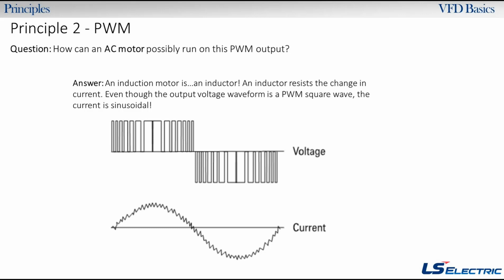Another thing to mention too is some people will connect up a multimeter to the output of the drive, and they'll wonder whether they should set the meter for AC or DC voltage. And you actually want AC, because most meters are true RMS meters, so that's root mean square. What it's going to do is add up and average out all these DC pulses. So if you set your meter to AC voltage, you'll have like 460 volts on your meter. Sometimes we'll get calls from people doing that, but their meter's still acting funky, and they're like, oh, I got 600 volts, I have 1,000 volts on the output, the VFD is bad. And usually it's just because, we're not showing it here, but this is going on and off really quick, and that causes little transients between these pulses, and those will be added in to that averaging of pulses with your meter. So sometimes meters will read that as like 1,000 volts because it's adding up those huge spikes.